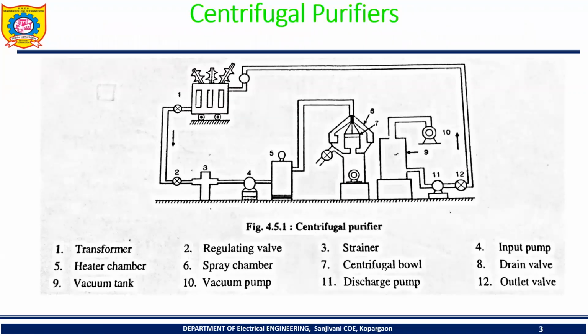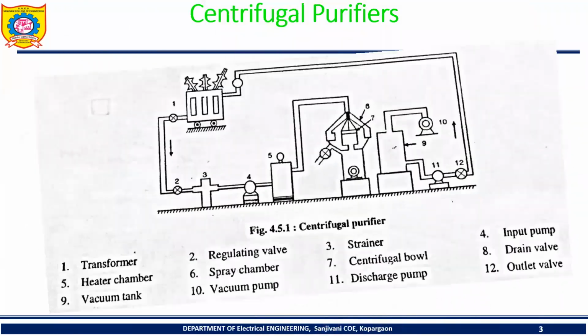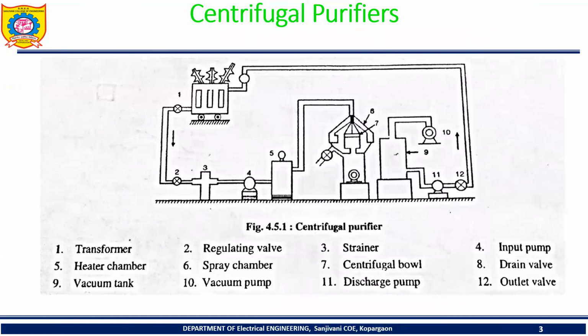Here in this centrifugal purifier, the overall construction diagram is as shown in the figure. First, the contents of a centrifugal purifier. Here the transformer tank, in which whatever oil is present is going to be filtered or purified. This is the regulating valve to regulate the transformer oil. Third one is called a strainer, in which we can add different chemicals for filtration purposes. Fourth one is nothing but the input pump. It is an electrical pump, the input pump to the heating chamber.